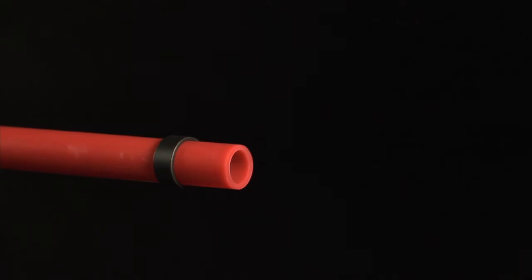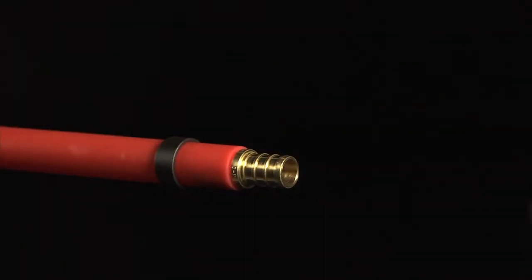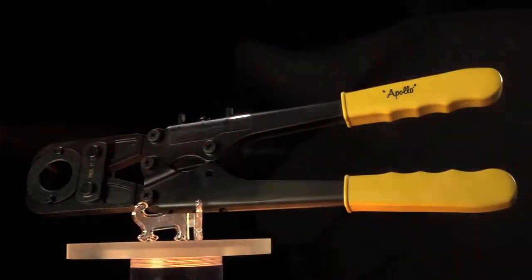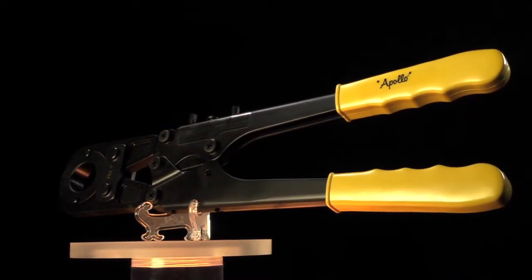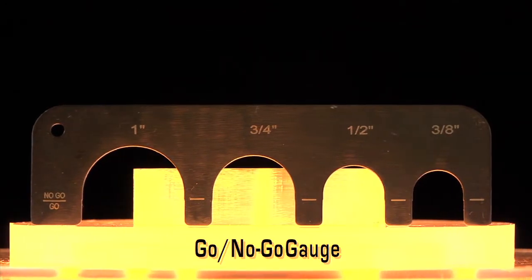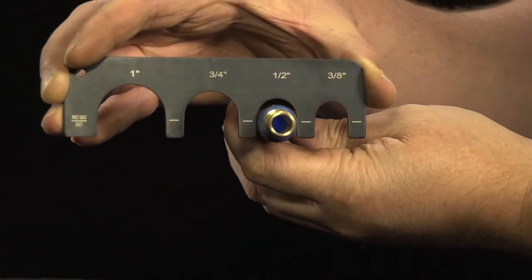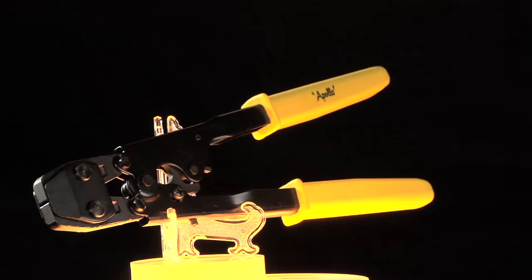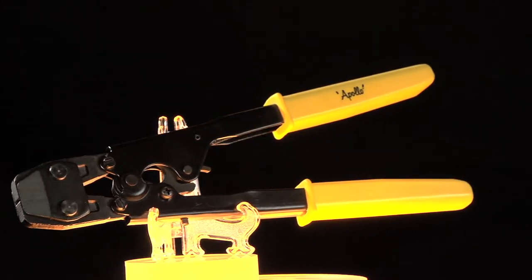Slide the ring or clamp over the end of the tubing. Insert the fitting into the tubing. Move the ring or clamp until it's one-eighth to one-quarter inch from the end of the tubing. Use the Apollo PEX crimp tool to crimp the ring around the tubing and fitting. Test the crimp with the Apollo GO slash NO-GO gauge to ensure a proper seal. Use the Apollo PEX pinch clamp tool to fasten the pinch clamp around the tubing and fitting.